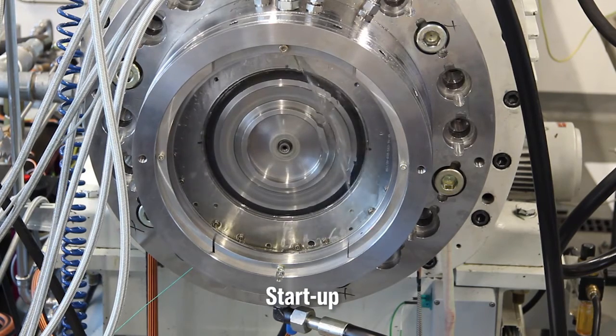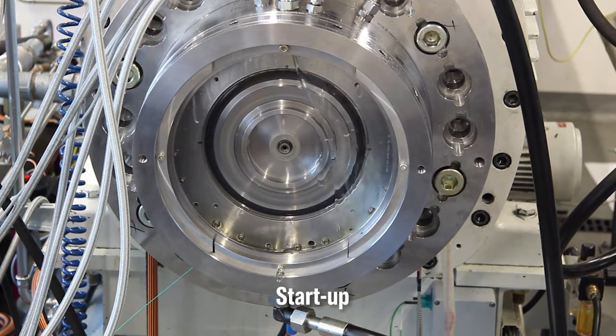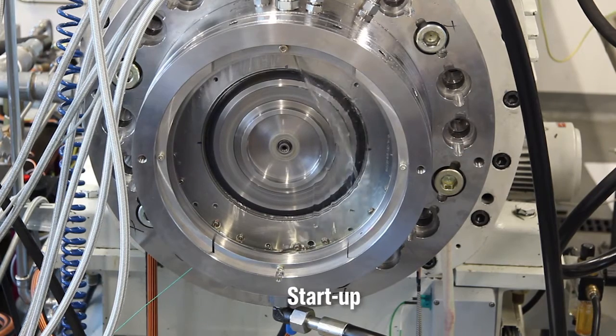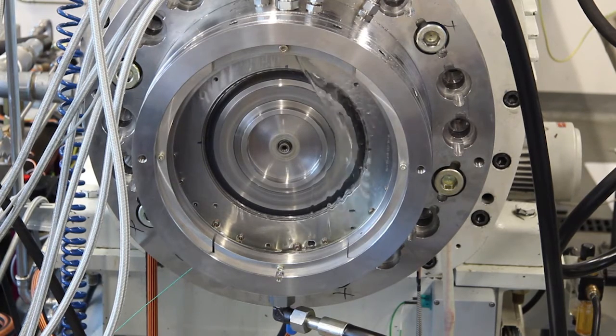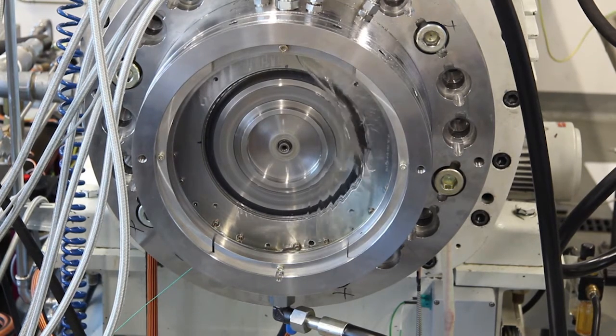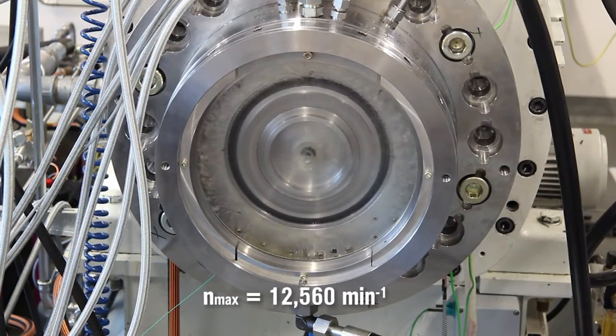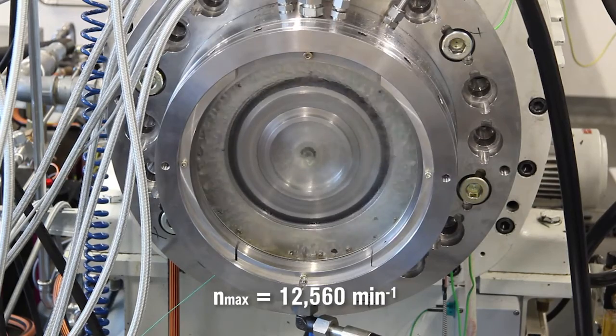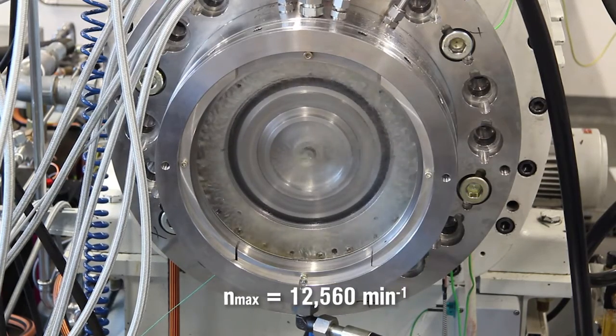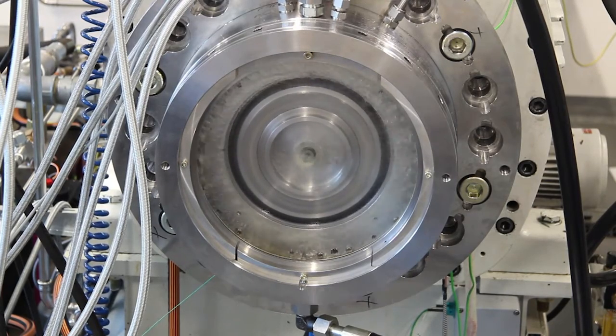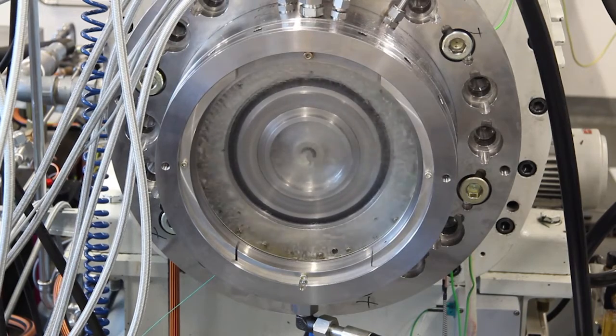After pressurization, the seal is started. The seal faces lift away from one another and run without contact or wear. The speed is increased to a maximum value of 12,560 revolutions per minute, which is equal to approximately 150 meter per second.